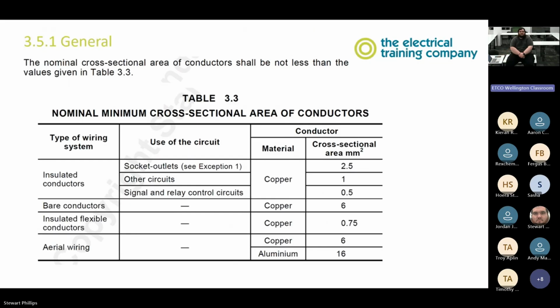So nominal cross-sectional area of a conductor shall not be less than the values given in table 3.3. Cool. So insulated conductors for socket outlets, copper cross-sectional area shall not be less than 2.5. Other circuits may be 1. Signal and relay control circuits may be as small as 0.5. So any bare copper conductors cannot be less than 6 mil. The minimal cross-sectional area of flexible conductors can be 0.75. Aerial wiring, copper 6, aluminium 16. So these are minimums. There is an exception for socket outlets, but we won't get into that.